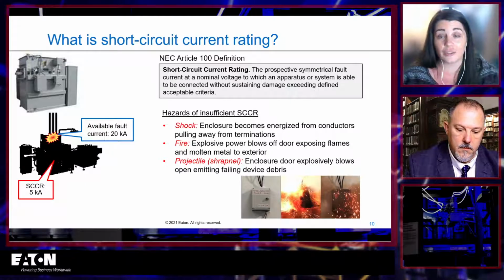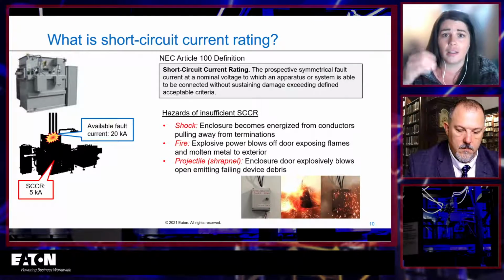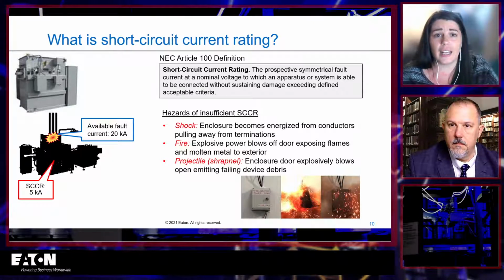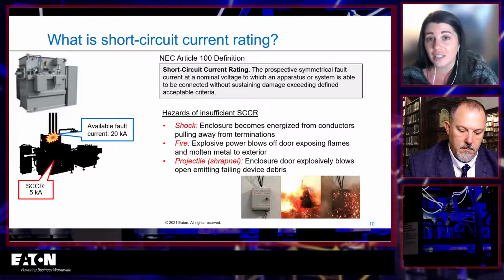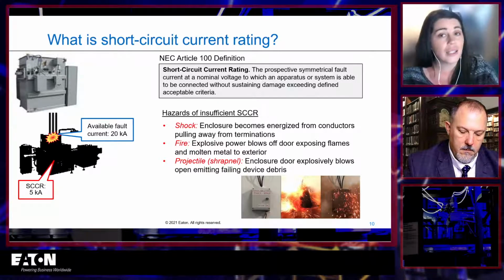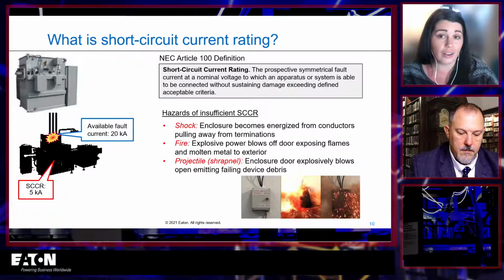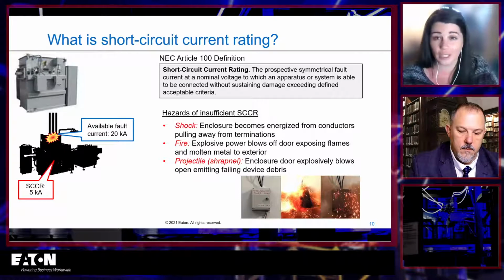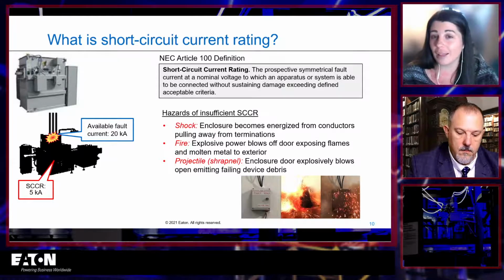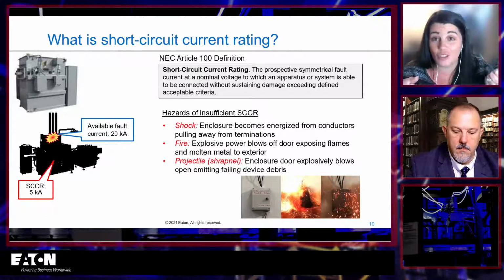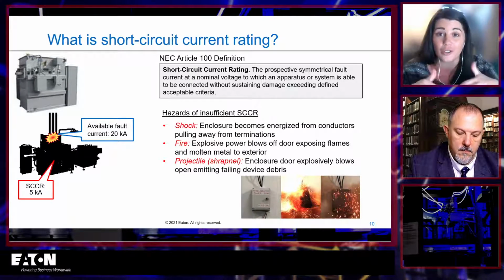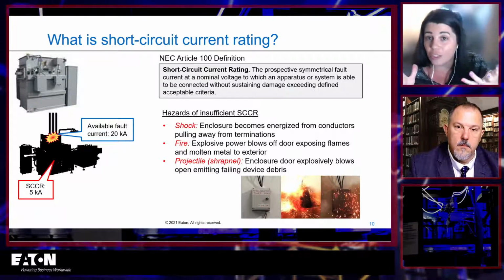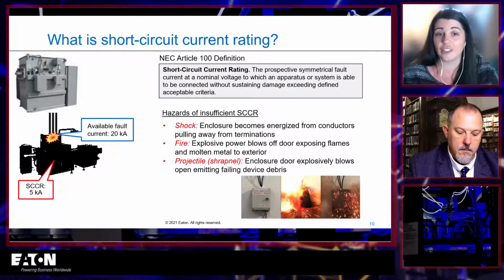A fire hazard, that's right, explosive power blowing off the door, exposing the flames to others. And the thing about a fire hazard that can be interesting is, depending on the particular UL standard you are trying to meet, you can create a fire hazard, but as long as the door doesn't blow open and expose you to it, you've passed the fire part of the SCCR test. So that's why sometimes you see specific pieces of equipment that have really beefed up hinges and doors, so that the door doesn't fly open. You can create the fire inside, and if the door doesn't blow open, you haven't created a fire hazard.